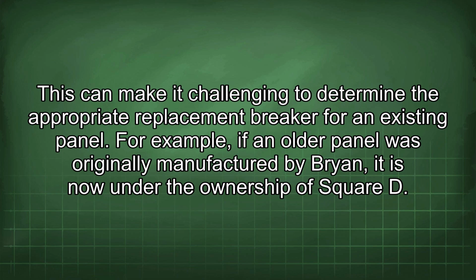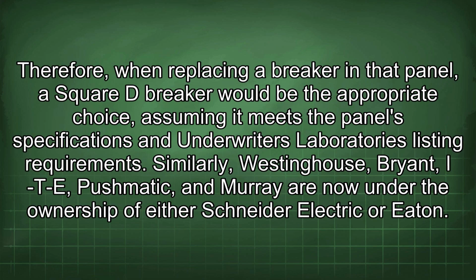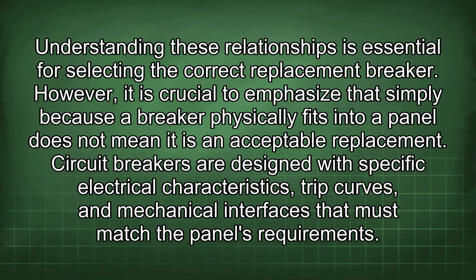For example, if an older panel was originally manufactured by Bryan, it is now under the ownership of Square D. Therefore, when replacing a breaker in that panel, a Square D breaker would be the appropriate choice, assuming it meets the panel's specifications and Underwriters Laboratories listing requirements. Similarly, Westinghouse, Bryant, ITE, Pushmatic, and Murray are now under the ownership of either Schneider Electric or Eaton. Understanding these relationships is essential for selecting the correct replacement breaker.